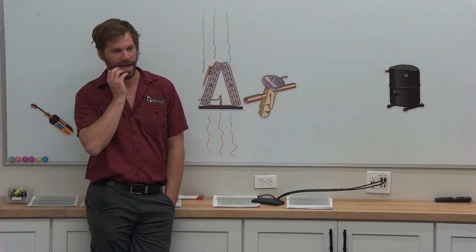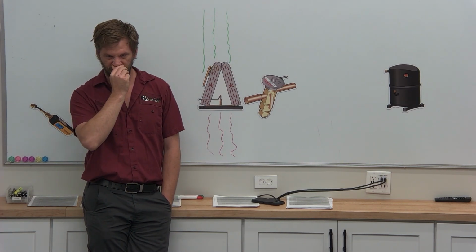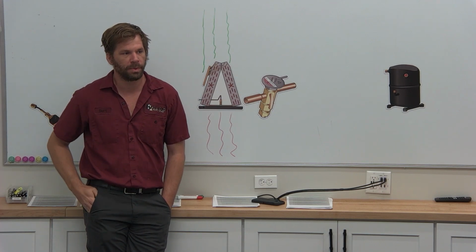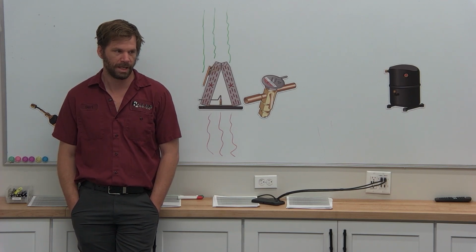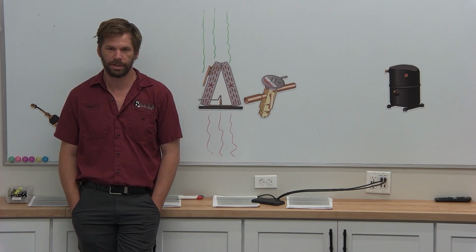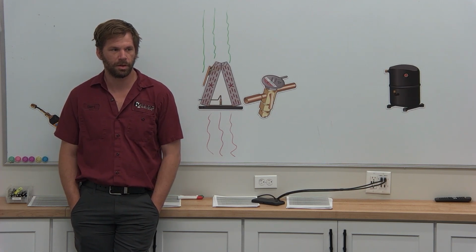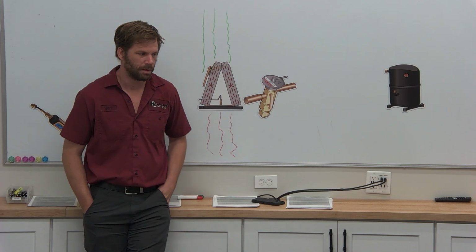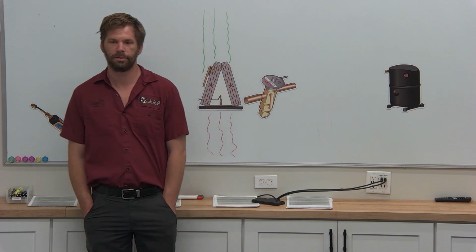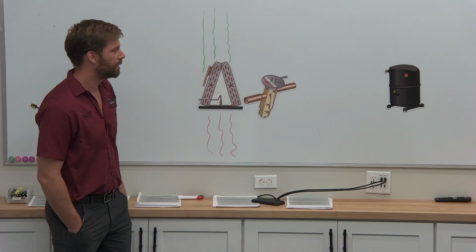And so I have got a lot of calls this year with very worried technicians spending way too much time on a call because their split was 14 degrees, and that's not 20. You know, hot pull down. Yeah, and we are either in a hot pull down, or it's 96 degrees outside and the home's 80 degrees. We have a poorly insulated home with a lot of humidity, and it is exactly on target. I had them enter this in or look it up on MeasureQuick, and our split was exactly what it was supposed to be. So let's talk about why that could happen real quick.